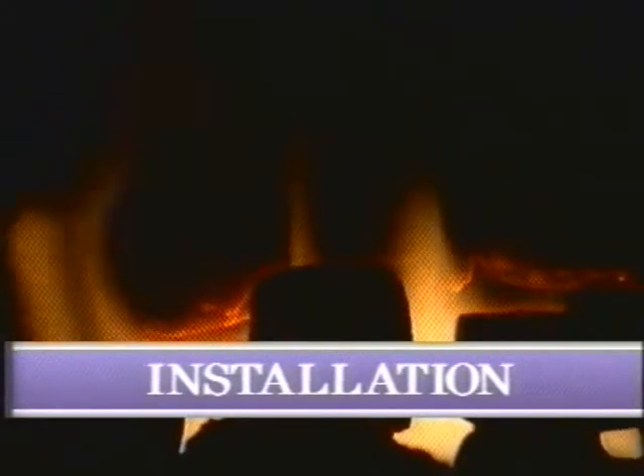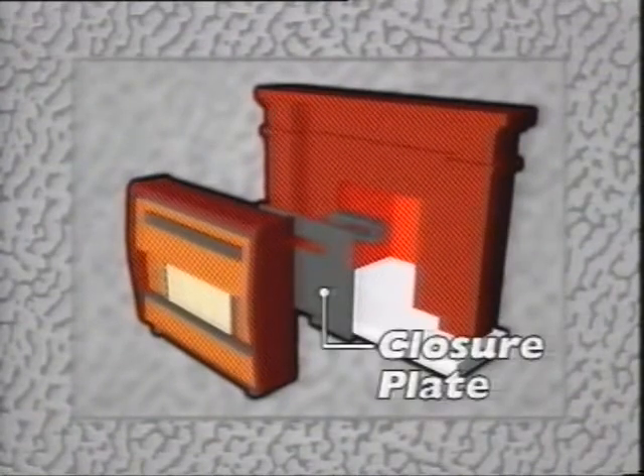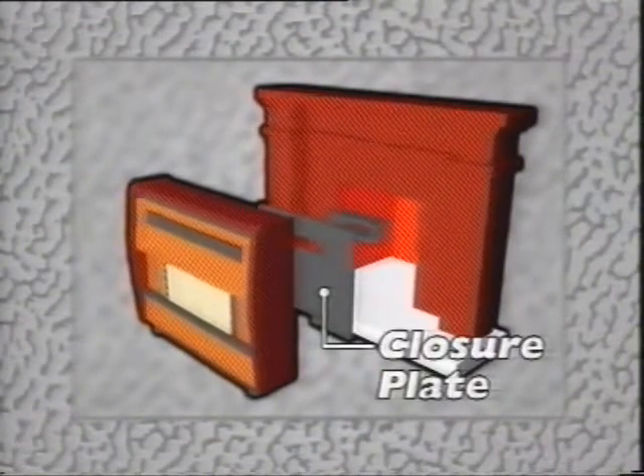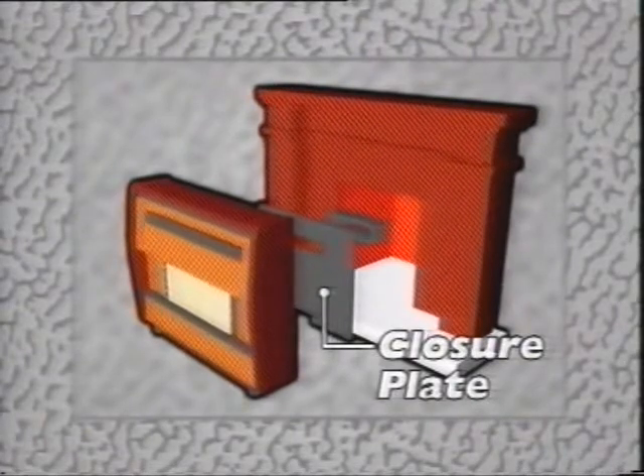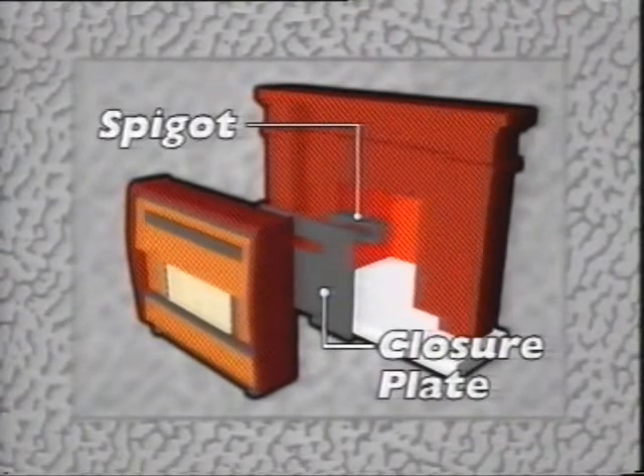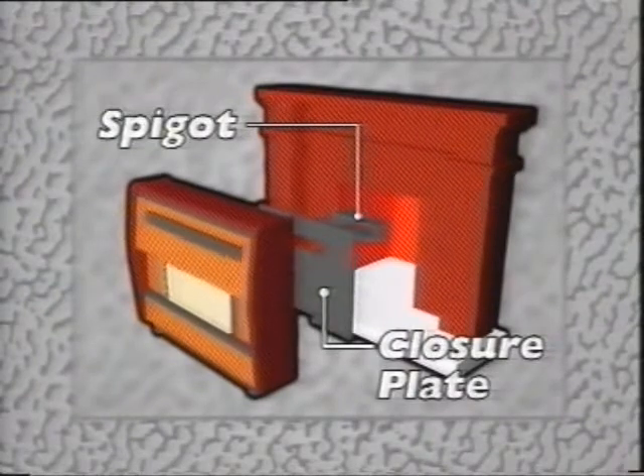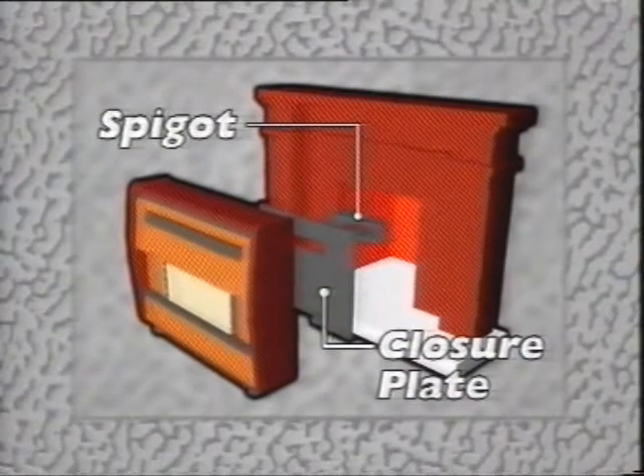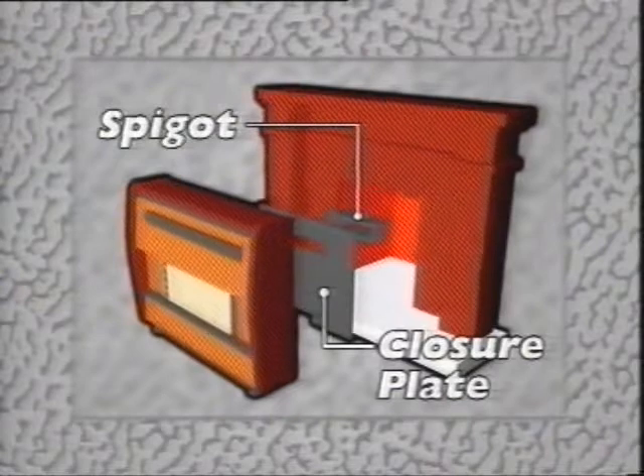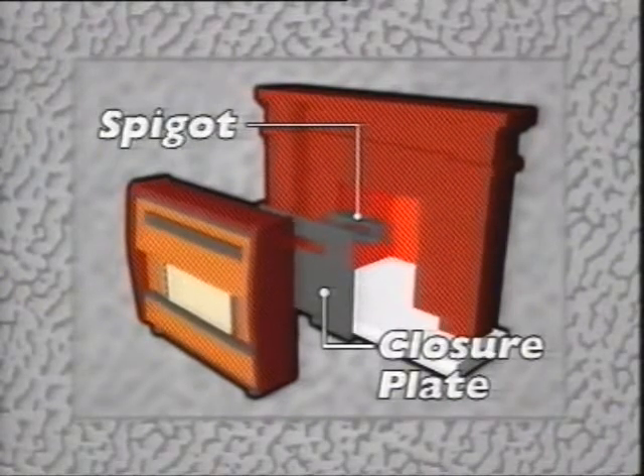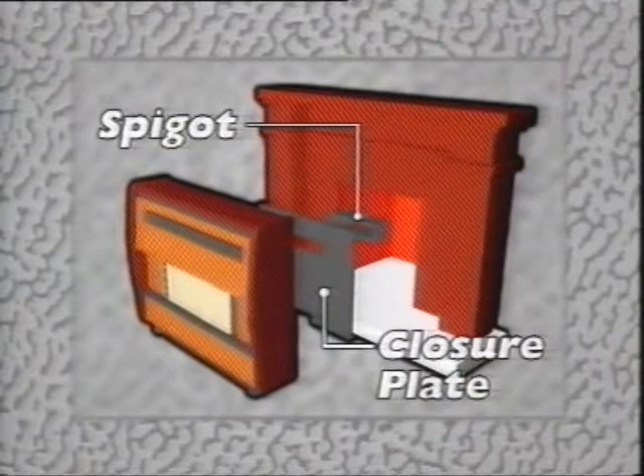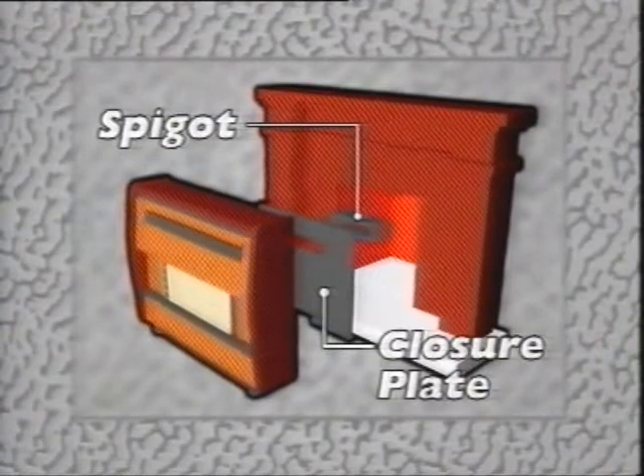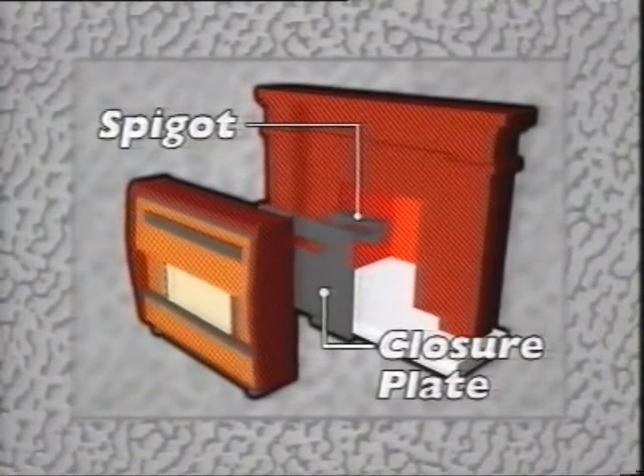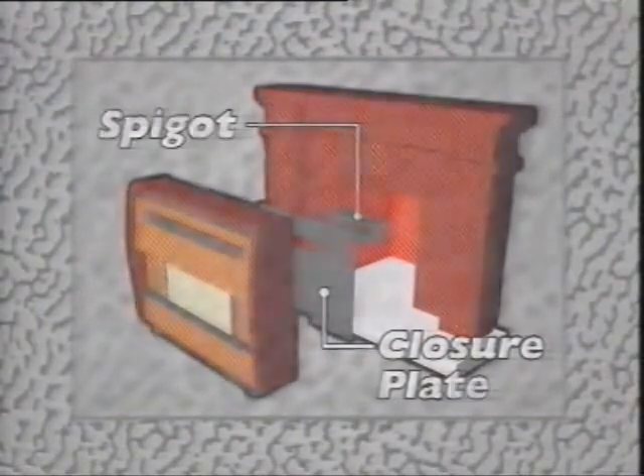There are several methods of installation, depending on the fireplace available. In each one, though, the fire has to have a closure plate behind it, sealed all round except for a relief opening. There must be a spigot to allow products of combustion to escape into the flue. However, remember to consult the manufacturer's instructions to see if and when a spigot restrictor is required. Below the spigot, there has to be a void big enough for that type of installation. The exact figures for these voids are listed in your written module.